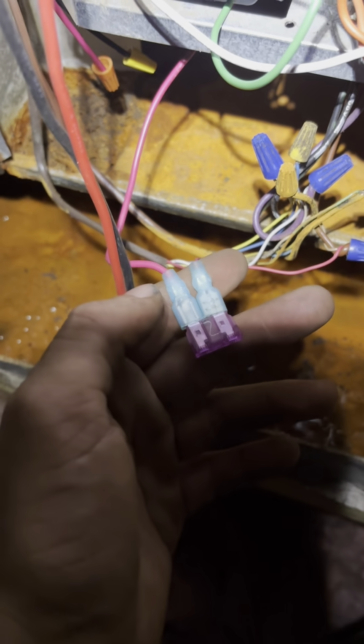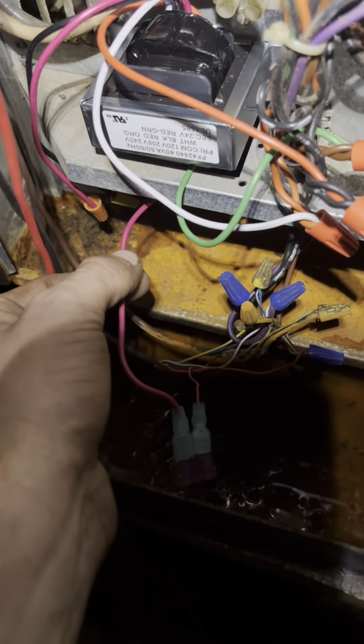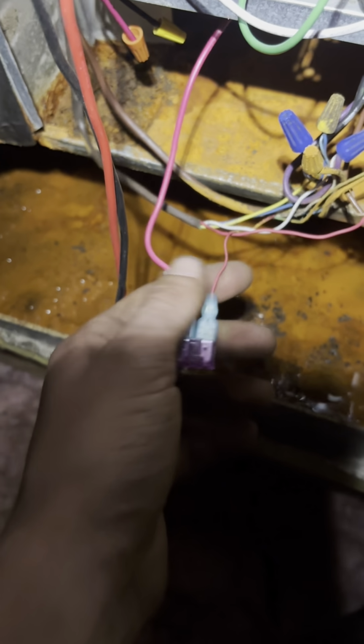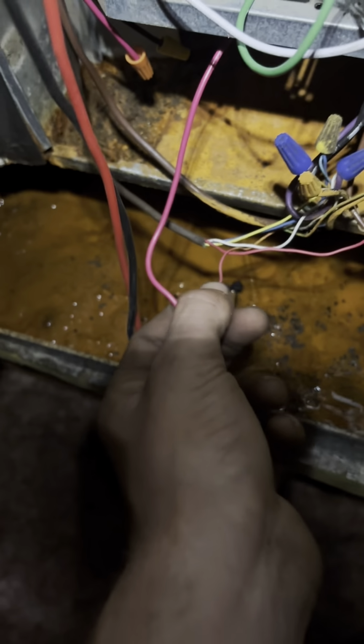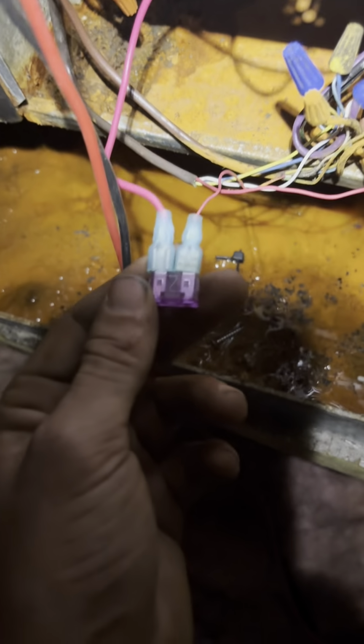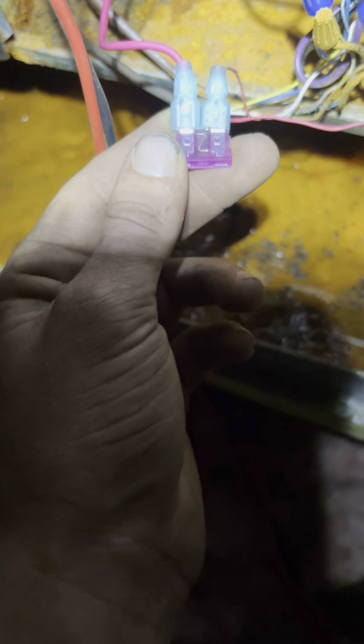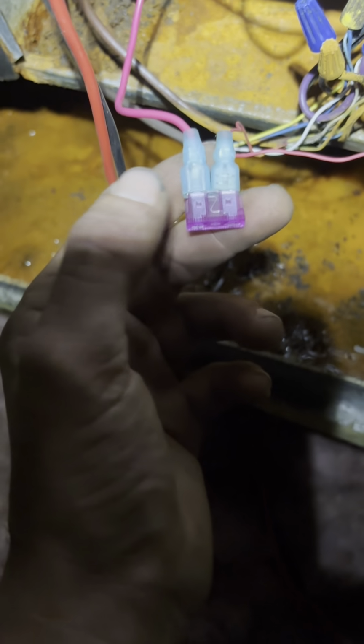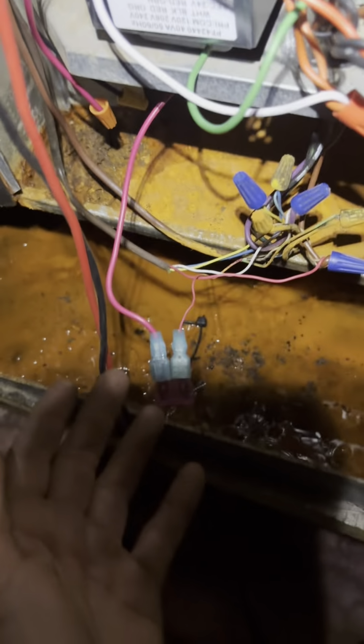Now, it's always a good idea before I turn on the power to take this red wire that we checked earlier, because it didn't have one of these. We need to put a fuse in between it. So this red wire right here, the little one, is going back to the thermostat. That's what feeds the thermostat power. That's what makes it tell the unit to come on and off. This is the one that feeds power from the transformer to that red wire. So when you break that and put a little 3-amp fuse on it, it'll blow this fuse before it blows this transformer again. So, all right, let's power her up.